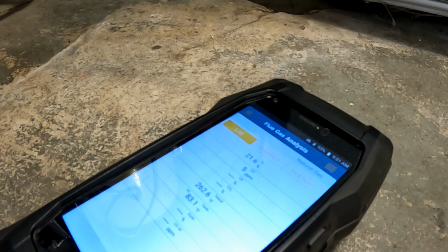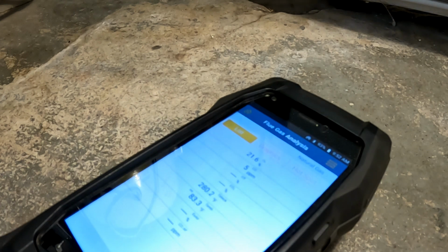We're going to start this right now. Draft hood's covered, sealed positively. Okay. And carbon monoxide only went up to 8. As you can see, it's dropping down quickly, parts per million. The idea is to get the carbon monoxide to drop down quickly and to control the startup with the air.